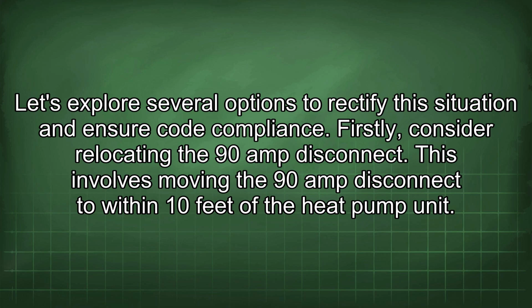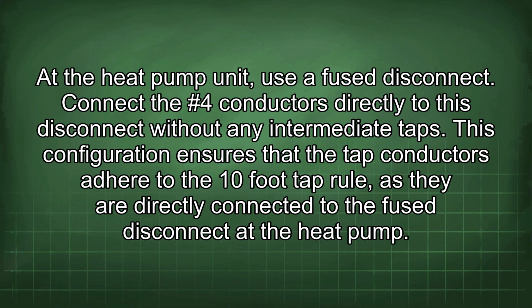Firstly, consider relocating the 90-amp disconnect. This involves moving the 90-amp disconnect to within 10 feet of the heat pump unit. At the heat pump unit, use a fuse disconnect. Connect the #4 conductors directly to this disconnect without any intermediate taps. This configuration ensures that the tap conductors adhere to the 10-foot tap rule, as they are directly connected to the fuse disconnect at the heat pump.